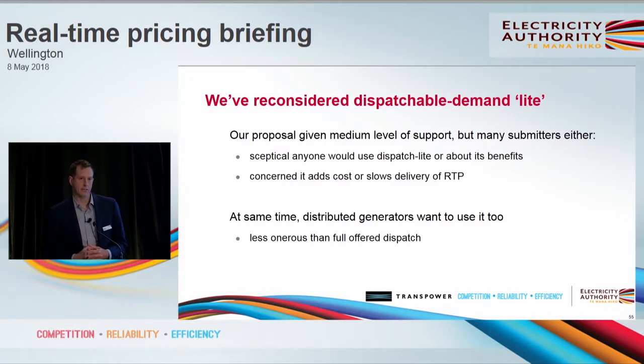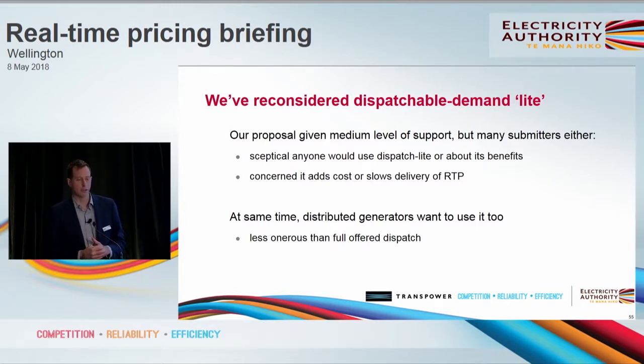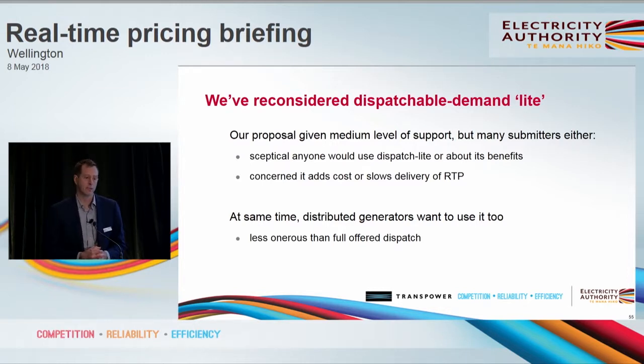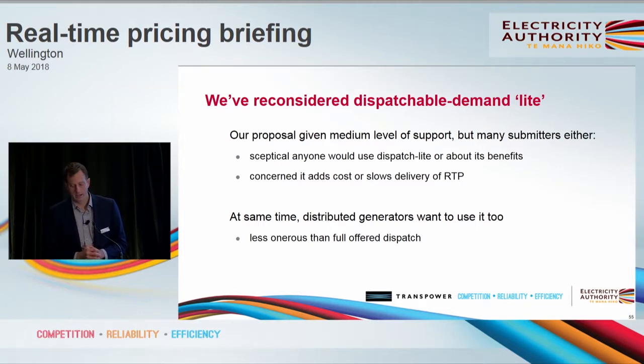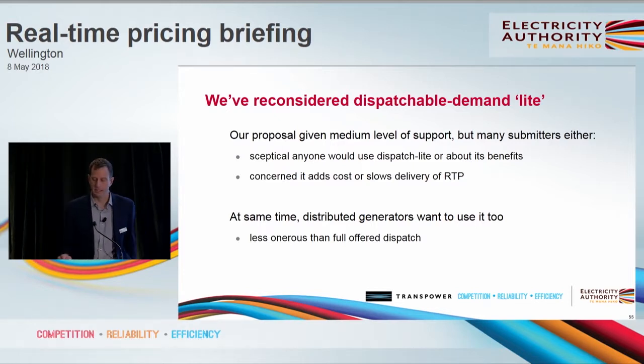The idea being that you could sign up, you could be dispatchable, you could still set the price, but you would have the option to say no if you received — rather than a dispatch instruction — something we introduced called a notification, with the trade-off being that you could say no not too often, and if you did do it too often you might be kicked out of the scheme, and you wouldn't be eligible for constrained on or off payments in contrast to full DD.